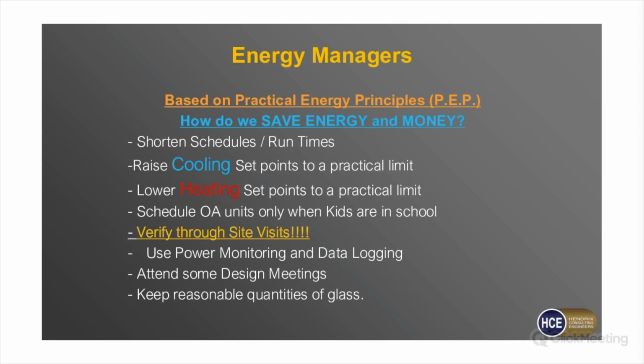It's really nice when your outside air is decoupled, because then you can schedule your outside air units for only when kids are there. You can run your heating and cooling from 6 to 5 because you've got admin staff early and cleaning staff late, but you're only required to have outside air for the kids when they're present, maybe 8 to 3 or 7 to 2. So you can pick up 3 or 4 hours of energy savings on those outside air machines by turning them off. Over time, if you're saving $20 an hour for 4 hours a day, times 180 or 200 school days, that really starts to add up to some money.